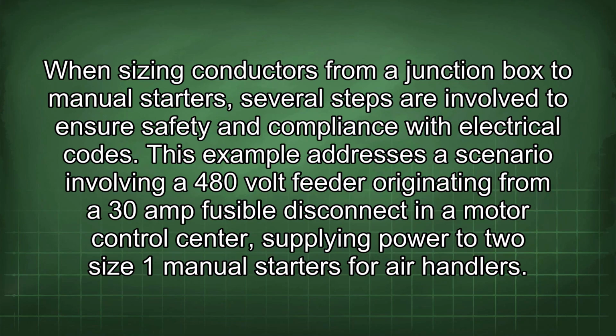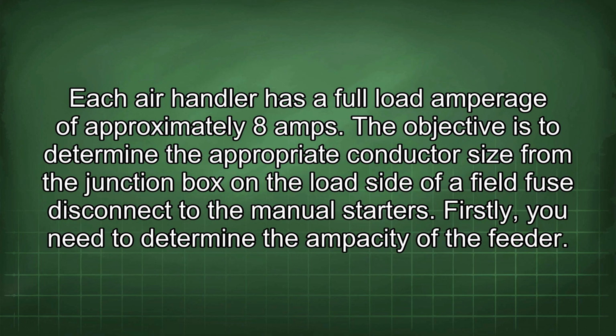When sizing conductors from a junction box to manual starters, several steps are involved to ensure safety and compliance with electrical codes. This example addresses a scenario involving a 480-volt feeder originating from a 30-amp fusible disconnect in a motor control center, supplying power to two size 1 manual starters for air handlers. Each air handler has a full load amperage of approximately 8 amps. The objective is to determine the appropriate conductor size from the junction box on the load side of a field fuse disconnect to the manual starters.